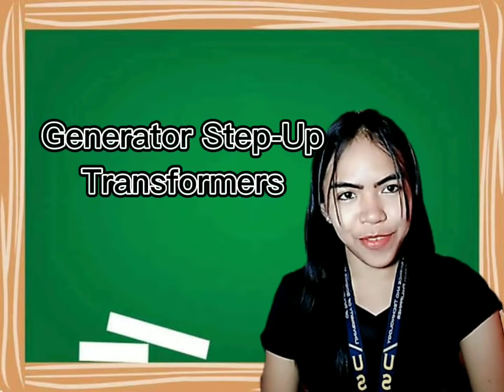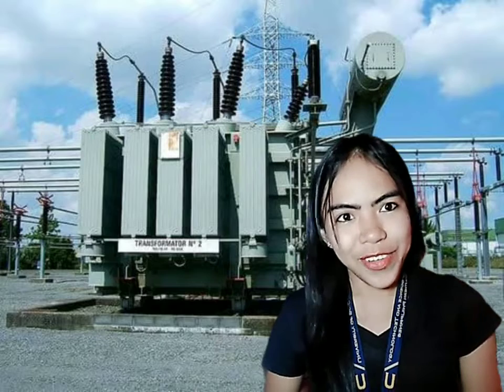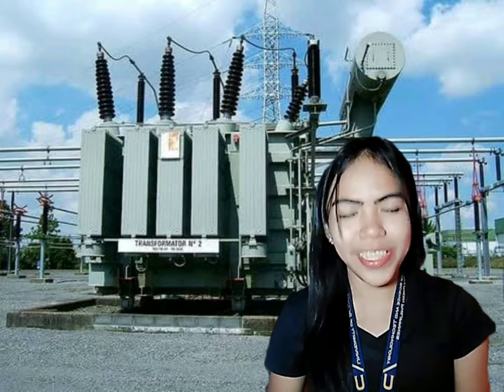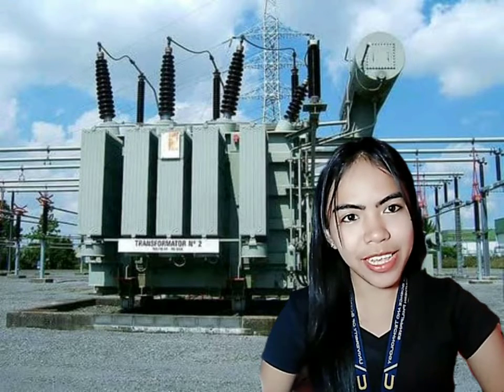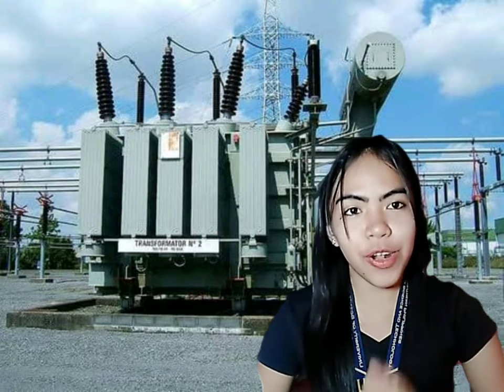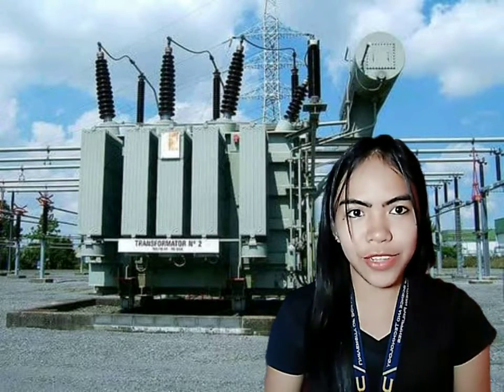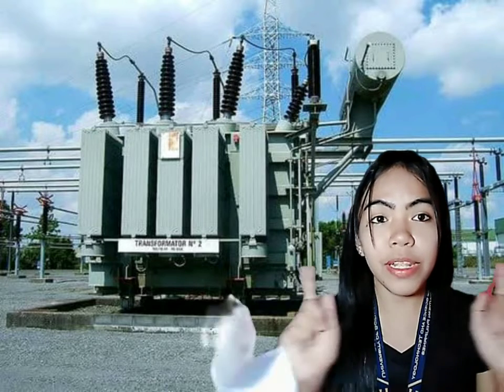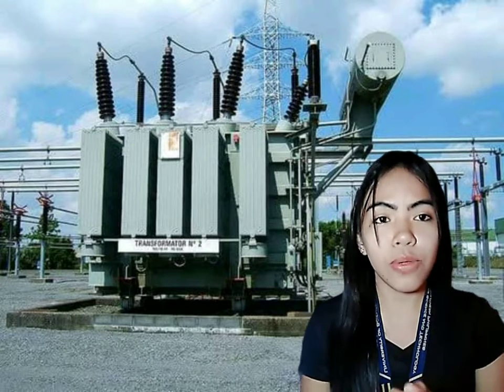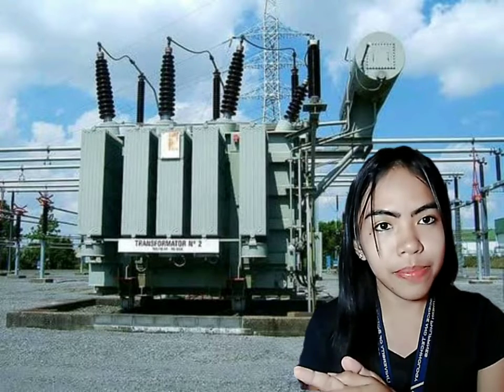The third type of transformer is the generator step-up transformer, which is the main or unit transformer. The GSU, or generator step-up transformer, is connected directly to the generator. It's also typically operated at a constant load close to its full rating.